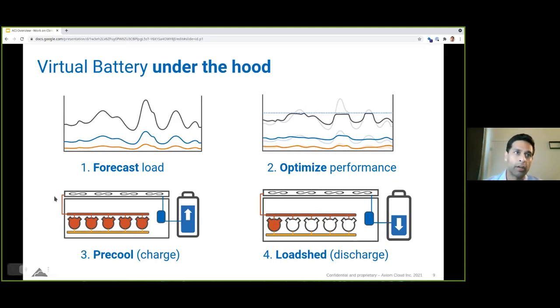Virtual battery will prepare for that curtailment, whether peak shaving or a demand response event, by pre-cooling low temperature cases. Low temperature cases for grocery are frozen goods, so it doesn't matter whether the store's ice cream is frozen at positive 5 Fahrenheit or minus 25 Fahrenheit—there's a huge range there. Getting colder, from virtual battery's perspective, is simply charging the system, and it doesn't affect the end product at all.